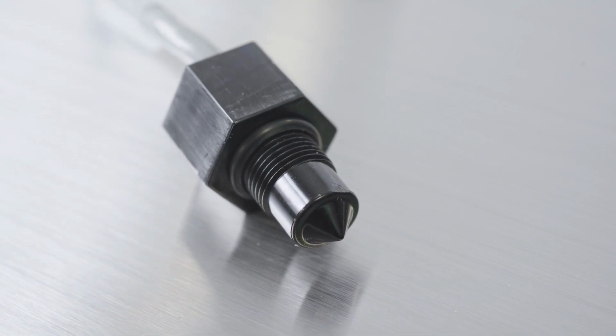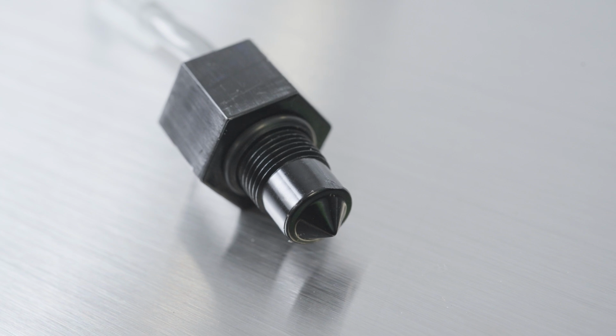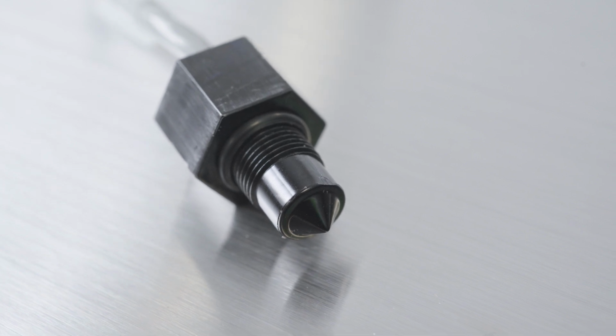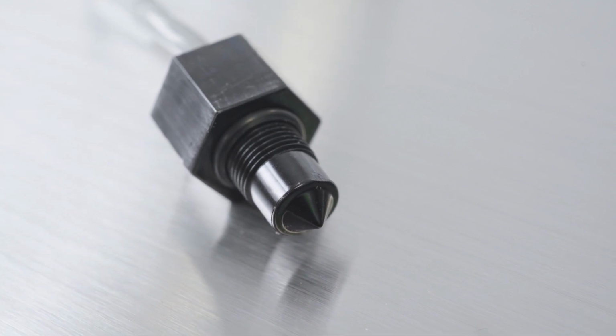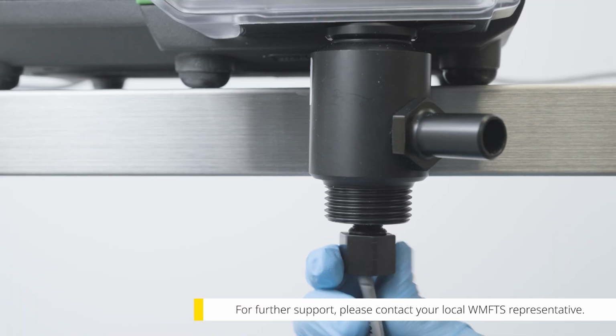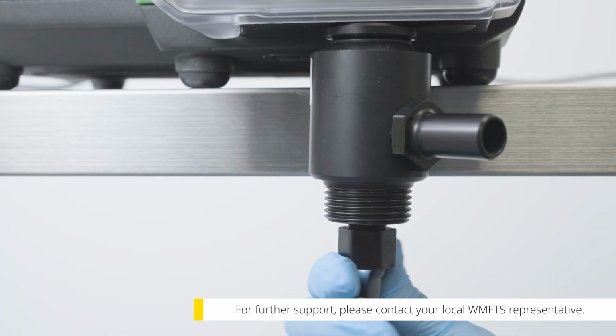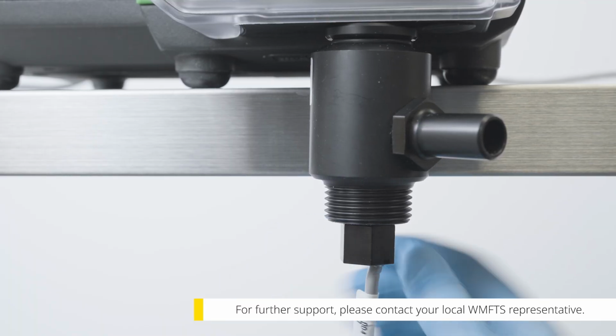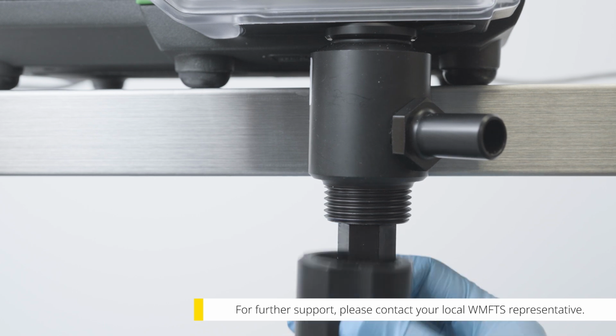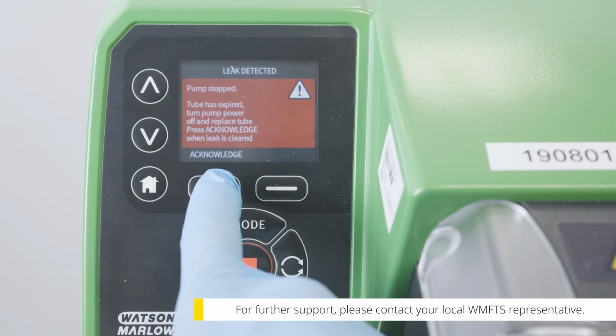For a float type leak detector, you'll need to follow your cleaning protocol to flush any fluid through to prevent prolonged exposure to your process chemical. Ensure the chamber is empty so the float resets. Once complete, screw the leak detector back into place and reset the message using the prompt on the keypad. And that's it. Thanks for watching.